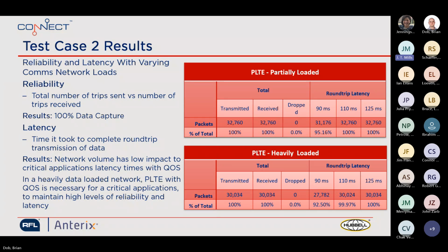I think Brian explained that a little bit. So in the top chart, we talk about partially loaded. This is the same data that we had in test case 1. But what we wanted to see is if we overloaded the communications network during a significant event, how that direct transfer trip data would be, if it's prioritized as level 1 priority, what that performance would look like. And what we saw is there was a minimal dip in performance.